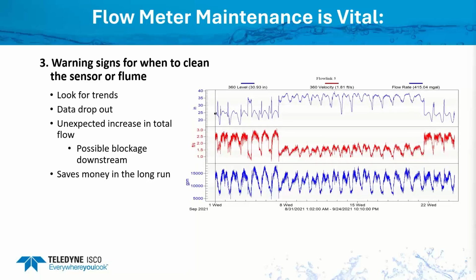Other things to look for is going back to looking at the trends. If you were only looking at the flow rate, down here in blue, you may not notice that there's any type of a problem, because the flows remained fairly consistent. But if you take a closer look at the other data that you have available to you, in this case, you see our level was averaging about 25 inches, and then it jumped up to around 35 inches. But then the velocity did just the opposite. What that's an indication of is that there was a gate or debris or something downstream that was restricting the flow going through there.